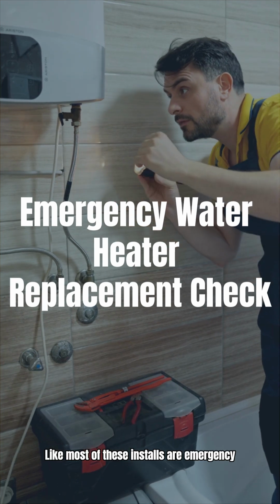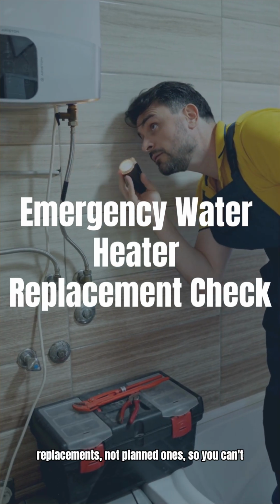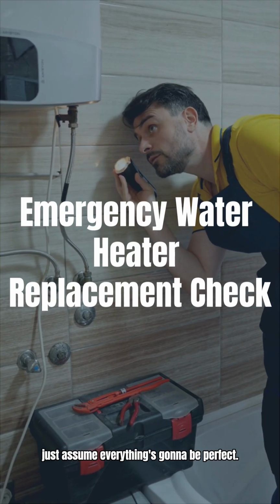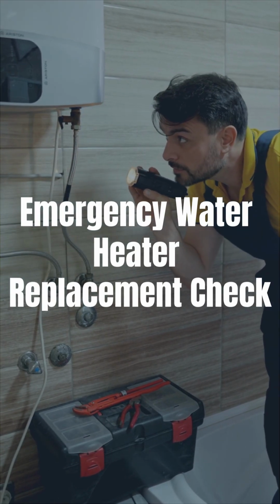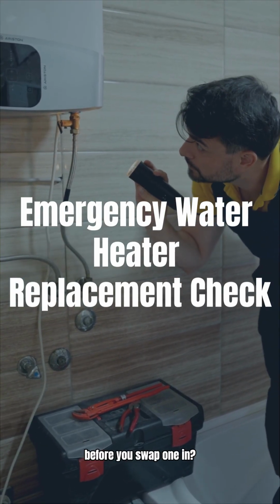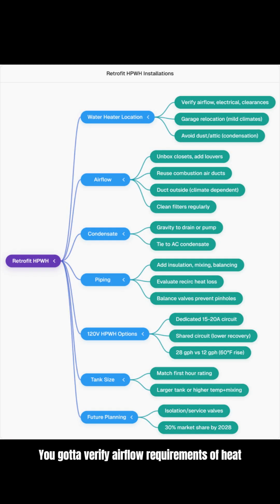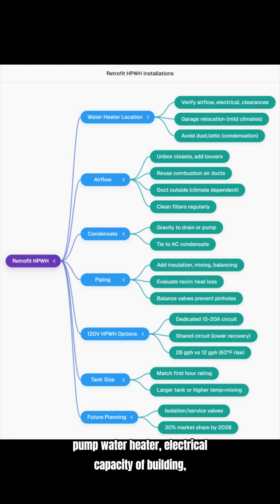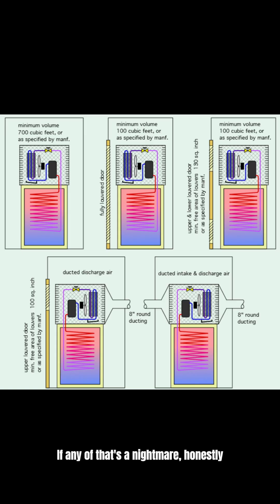Like most of these installs are emergency replacements, not planned ones, so you can't just assume everything's going to be perfect. What do you actually need to check before you swap one in? You gotta verify airflow requirements of the heat pump water heater, electrical capacity of the building, service clearance requirements, and how you're going to handle the condensate drainage. If any of that's a nightmare, honestly you might pick a different heater instead of forcing it.